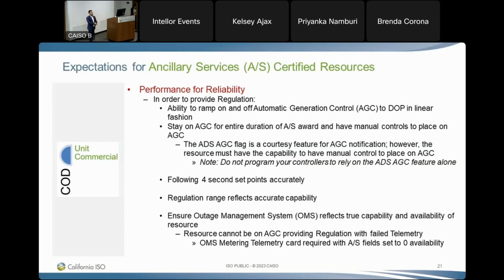At that switchover, there are times where the controllers on the batteries aren't set to ramp in a linear fashion, and they'll jump on and basically spike the interconnection. It could potentially spike the interconnection, but we see the jump. That's something they need to understand: when they set the controller up, they need to ramp into that in a linear fashion. So if you get a test question on anything about batteries, linear fashion is what you answer. Instantaneous is the wrong answer every time, okay? Perfect, I'm glad you guys are paying attention here.